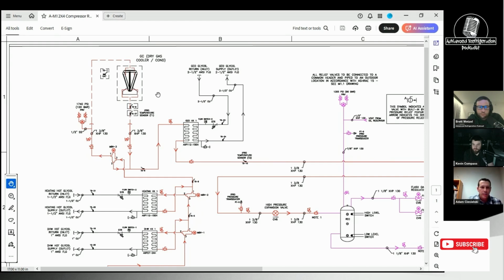But in that situation, it does not happen quickly. It can take an hour from the onset of things. Ambient temperatures don't change that fast. So as the temperature drops, it may take 30 to 60 minutes from running perfectly fine until it basically falls over. So my point being is, the most successful setup of fan control and/or this 3-way bypass is to go very slow. Do not make it aggressive.